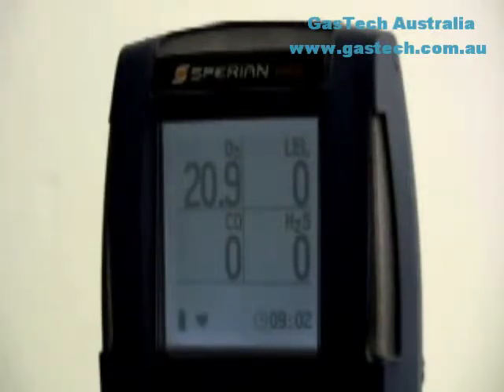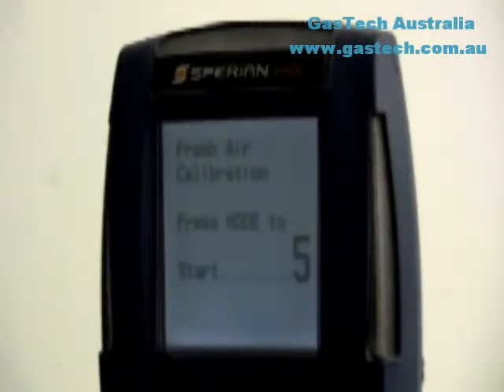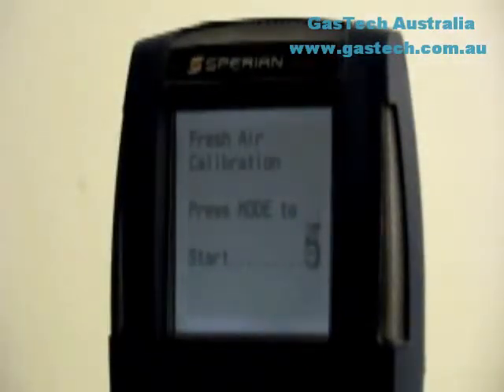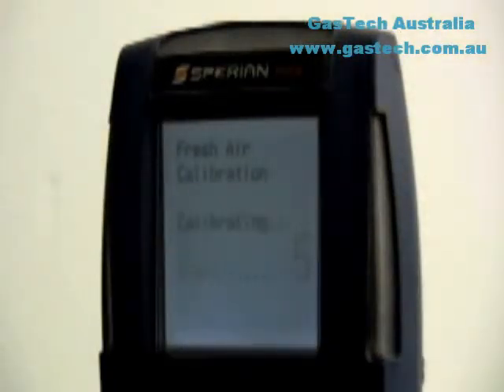Press the mode button 3 times within 2 seconds to initiate the fresh air zero calibration sequence. To return to the current gas reading screen and bypass the fresh air zero calibration, allow the clock to count down without pressing the mode button. To initiate the fresh air calibration, press the mode button before the unit completes the countdown.